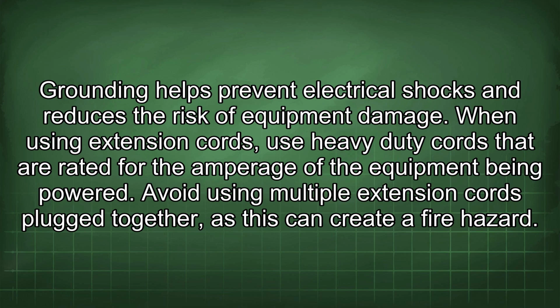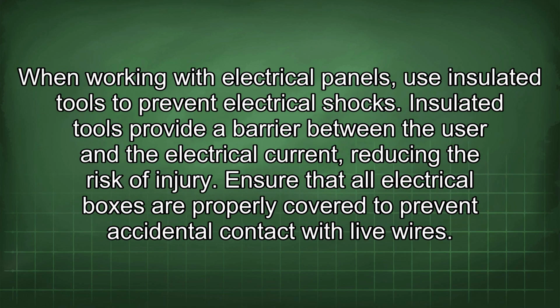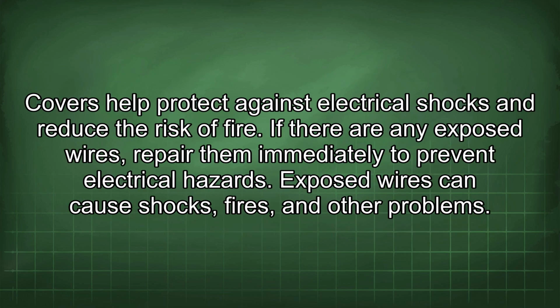When using extension cords, use heavy-duty cords that are rated for the amperage of the equipment being powered. Avoid using multiple extension cords plugged together, as this can create a fire hazard. When working with electrical panels, use insulated tools to prevent electrical shocks. Insulated tools provide a barrier between the user and the electrical current, reducing the risk of injury. Ensure that all electrical boxes are properly covered to prevent accidental contact with live wires. Covers help protect against electrical shocks and reduce the risk of fire.